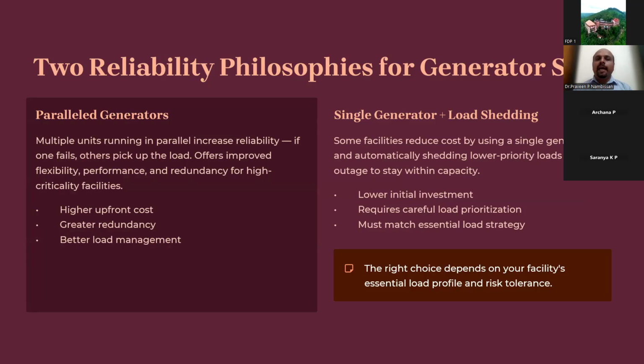There are two reliability philosophies for generator sets: parallel generators, and a single generator with load shedding. Parallel generators run multiple units together for increased reliability; if one fails, the other automatically picks up the load, though this comes with a high upfront cost since two systems are needed.